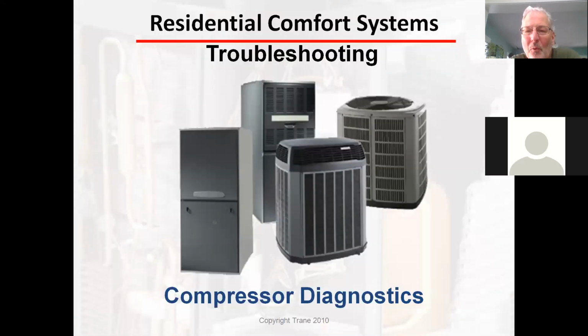So this morning, what I want to talk about is compressor diagnostics. We usually do a class about how to check superheat and subcool, and we're going to do something a little different this spring. It's how to verify you've got a fan that's working properly or your compressor's working properly, how to troubleshoot. I've got a video that's really good. It talks about scroll compressors, and then there's a new generation two-step scroll. I don't know if we've spent any time on that in the last couple of years, so we're going to talk about that a little bit too.